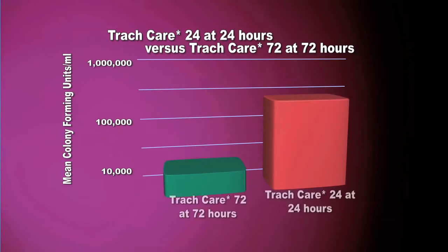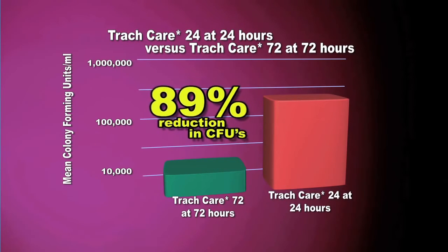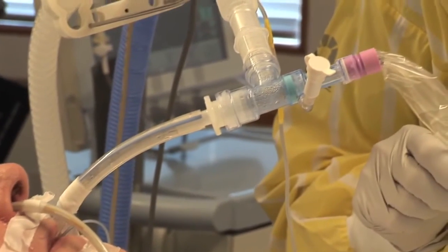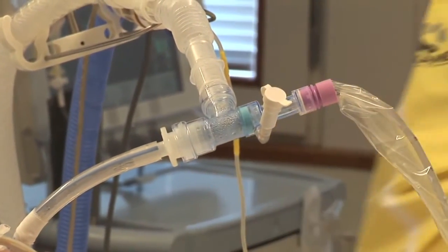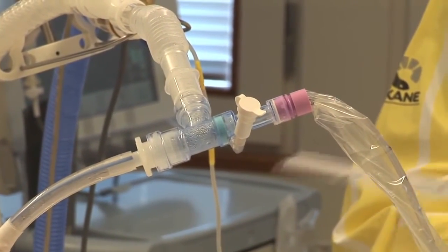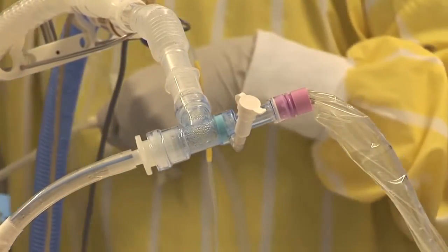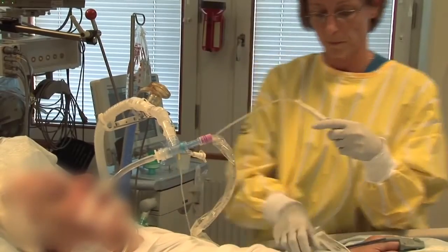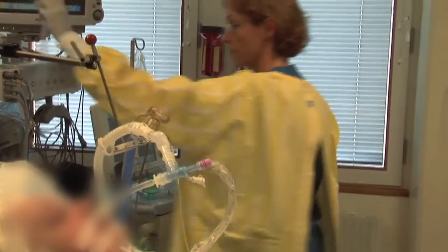This results in an 89% reduction of residual colony forming units on the catheter after three days in situ, when compared to our standard 24-hour catheter after just one day. When shortening the ET tube with Trach Care in situ, the catheter must be withdrawn with the black ring visible inside the sleeve to avoid cutting the suction catheter. Some hospital protocols call for the ET tube to be cut at the lips or the teeth of the patient.